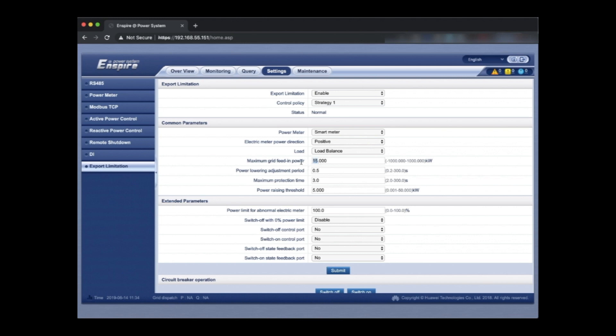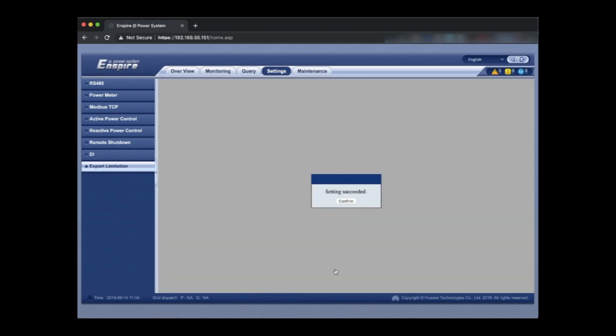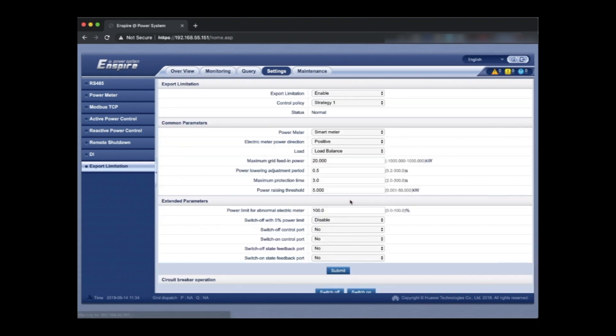And then press submit and we've now completed export limitation on the smart logger which will control the power output of the Huawei 29.9 kilowatt inverter. And there we go. Succeeded. Confirmed. All done.